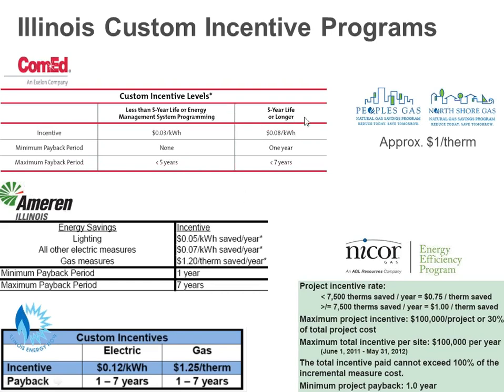Because an ERV has more than a 5-year life - more like a 20-year life - you would fall under that second column under ComEd, where you get 8 cents for each kilowatt hour saved during the first year. You would also be able to go on the gas side of the equation, since the ERV saves you both gas and electric, and go to your gas company to get anywhere from 75 cents to $1 for each therm saved during the winter heating season.